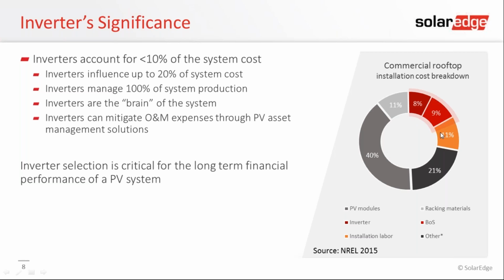Let's say we buy the cheapest inverter we can find and it's 600 volts, whoever it is. It could directly impact your system cost by up to 20%, because if we buy a 600 volt inverter, that means our string lengths are limited to 600 volts, which means we have a lot more copper on that rooftop. It could be a pad, it could be a concrete pad, it could be many things. So when you're looking at inverter comparisons, you can't just consider inverter to inverter. It's more than that. You have to look at the entire system cost, okay?